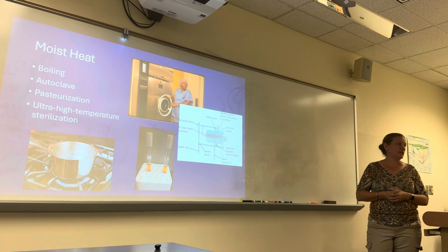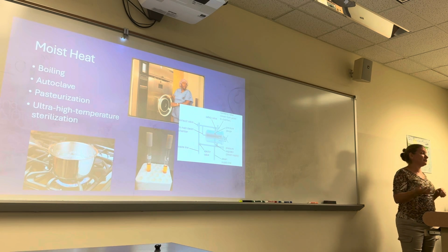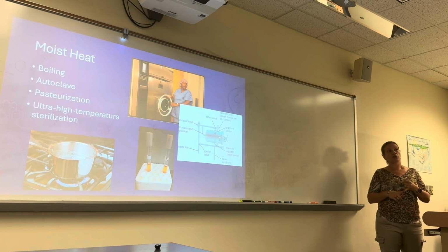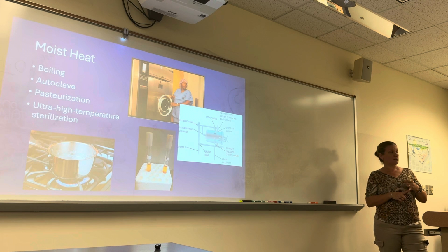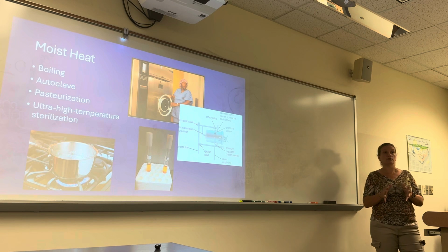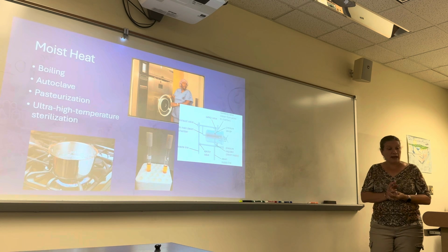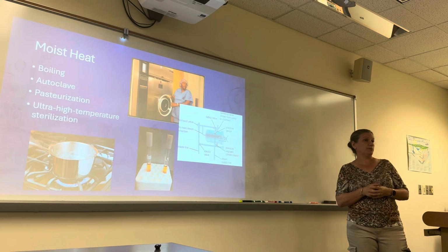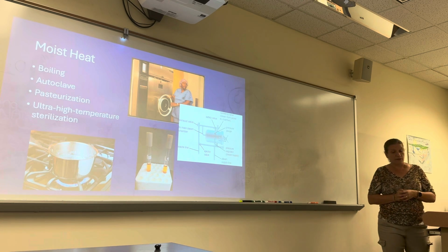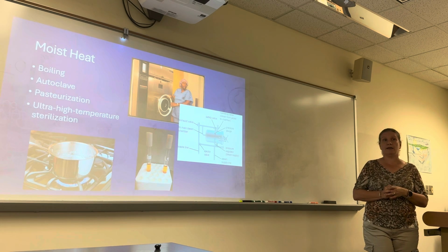And you do have testing that you do in order to verify this. Depending upon your facility, to ensure that the autoclave is working, because once you autoclave the biohazard material, that material can go into the regular waste disposal, because everything has been killed. So facilities that use autoclaves do have to demonstrate that the autoclave is working properly. There are different ways that you can do that, and it depends upon the facility as to what the regulatory requirements are. I don't know off the top of my head in the hospital setting.